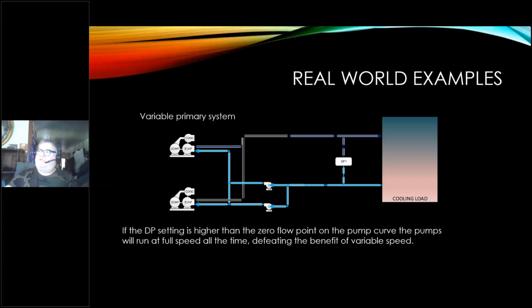So you'll never see that pressure differential at the pump. Out in the system, it's going to be lower than what you'll see at the pump. But that's a way of telling you, am I still moving water out here? If I get a pressure differential on the system, I know I'm moving water, and it's working against some resistance out there in the system. But if my pressure differential increases, that means the system has changed, and I can actually back the pump down to match that change, to get a better match on my flow required versus what I'm able to pump out of the pump.